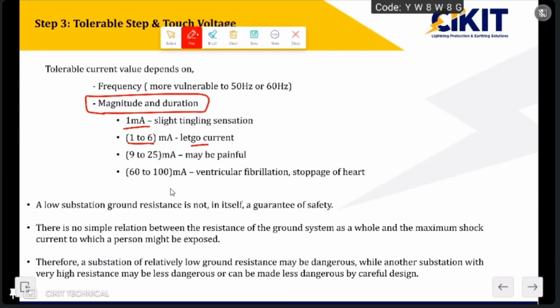But if the current magnitude is 25 milliamps or more, it will be more painful. And if the current magnitude is 60 to 100 milliamps, it will be very dangerous. It may result in ventricular fibrillation or stoppage of the heart also. So here everywhere the current rating is in terms of milliamps. Because of the step and touch voltages, if a few milliamps flow through our body, we may feel electrocuted. That is the reason we are giving more importance to the step and touch voltages. If a current of 30 milliamps is flowing through our body, we may get electrocuted. So the magnitude of 30 milliamps itself is sufficient to cause sufficient damage to our body.